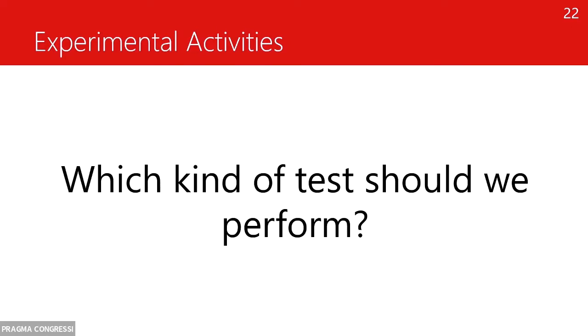Now, as Professor De Maria explained yesterday, if you want to go on the market, we have to perform some tests in this direction. So we started to search the MDR for which tests we have to do. Nothing, because there are no standards that tell you which kind of test you have to do for this device. If you want to make a new heart valve prosthesis or a ventricular assist device, you have, I think, from 3 to 6 standards that explain not only which kind of tests you have to do, but the setup that you have to build if you want to use your own setup, and the equipment that you have to use for the measurement.